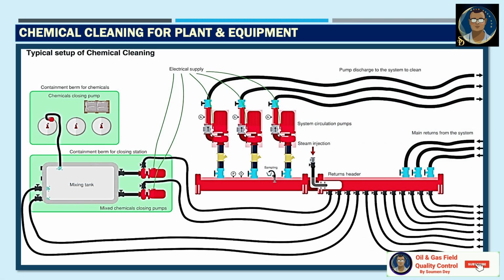Where and why is chemical cleaning required in plant piping and equipment, based on standard best practice of the oil and gas industry? Chemical cleaning shall be conducted for in-plant piping, fin-fan tubes and heat exchanger tubes or plates for the services I will mention now. It can be done during pre-commissioning after hydrostatic testing. The objective is to remove oil, grease, preservatives, rust, mill scale and corrosion products.